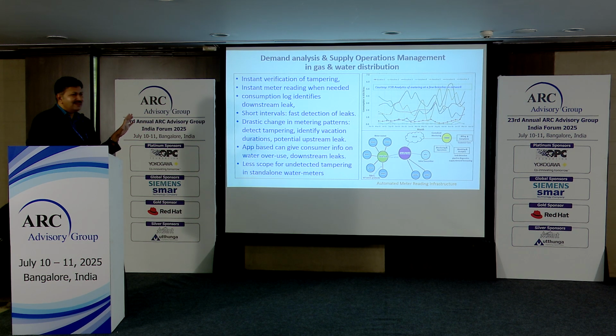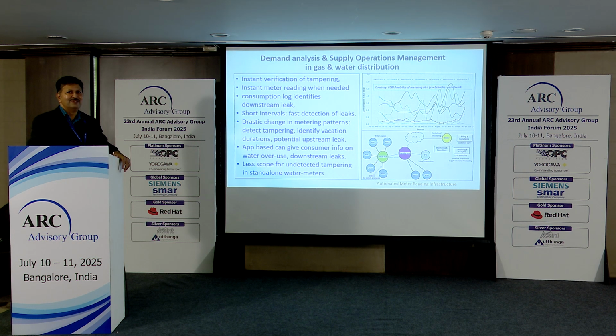Another aspect is that IoT based mechanisms are used in all the flow measurement, flow metering for water distribution as well as gas metering, because most of the metering for distribution is in rural, I should say semi-rural or urban or semi-urban areas, where connectivity is no longer an issue nowadays compared to the earlier times. So people have been going in for AMRs and IoT based water meters with all these kinds of protocols, so that we can now connect more places cheaper, and you could have consumer IT systems where you can generate automatic bills and make them available to them.